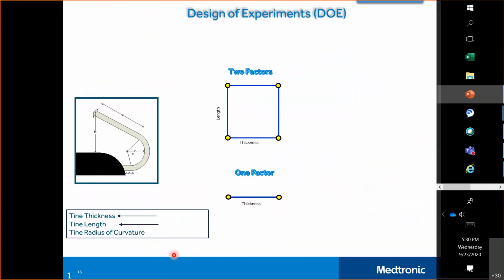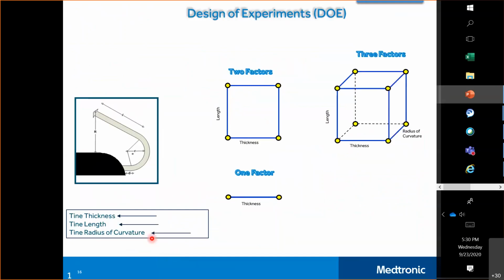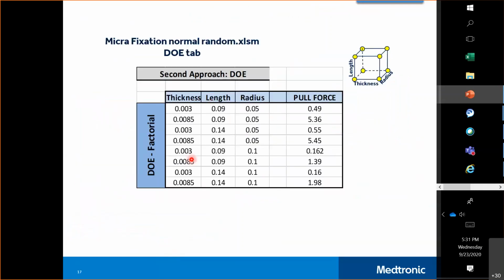With 3 factors, tine thickness, tine length, and tine radius of curvature, geometrically we represent it with a cube: low and high thickness, low and high length, low and high radius of curvature, with 8 combinations. So here are those 8 combinations that they ran through the finite element analysis mechanical simulator. For each of those combinations of thickness, length, and radius, the finite element analysis, which was calibrated to correspond very close to what they saw with porcine heart tissue, predicted the pull force, the attachment force. But at this point it is still a deterministic model.